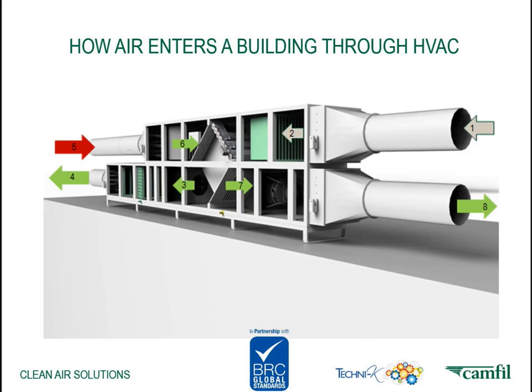What we are going to show you here is how air enters your facility through an air handling unit. This is a schematic drawing of the HVAC unit and its air movement. As you can see with the arrow 1, air is coming from the outdoor area and it is untreated. Air is being filtered through the classified filter in one or several filter steps, as we can see in arrow 2. In arrow 3, air passing through a heat exchanger. In arrow 4, air supplied to the room. In arrow 5, air exhausting from the room. In 6, exhaust air is being filtered through a classified filter in one or several filter steps. At point 7, air passing through a heat exchanger. At point 8, it is filtered through the heat exchanger and returned as air to outdoor air.